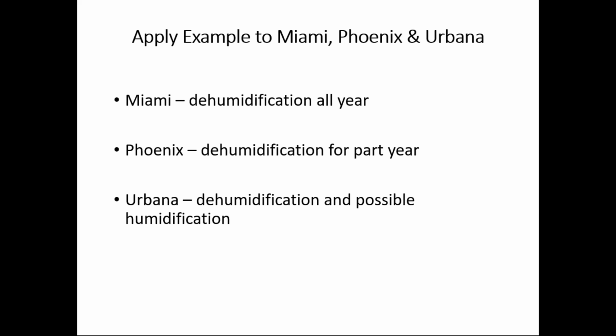We'll look at the peak summer and then the winter, if you can call Miami as having a winter, and look at the characteristics as far as the moisture management. What we'll find is Miami has dehumidification all year, and as dry as we think of Phoenix, it does have a mini monsoon season, as parts of the Southwest do, that requires some dehumidification. And then basically no humidification should be needed in Phoenix for the winter time. And then Urbana, where dehumidification for sure is needed in the summer, and then possibly needed, depending on the construction of the house, humidification in the winter.